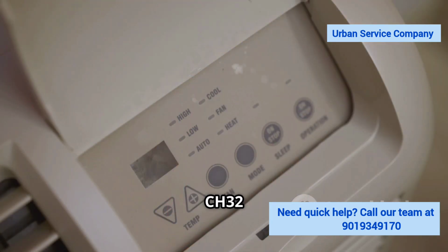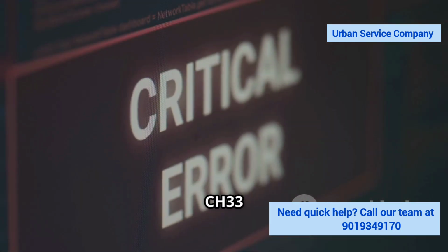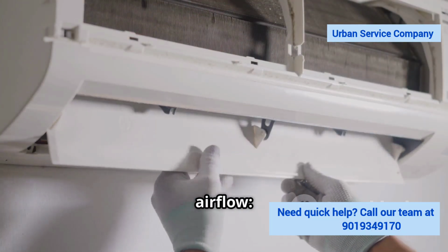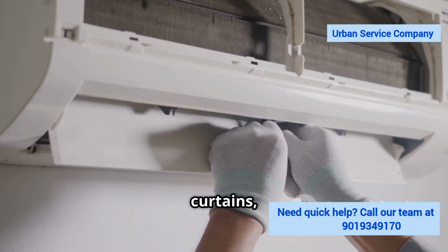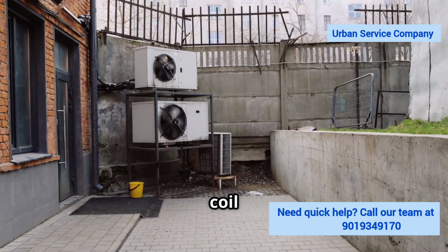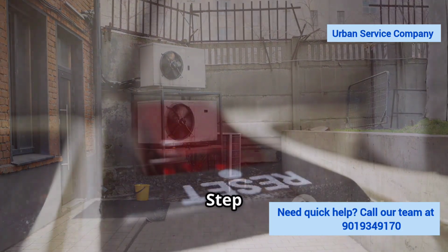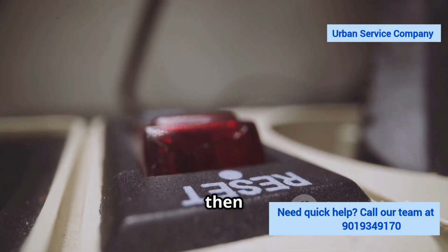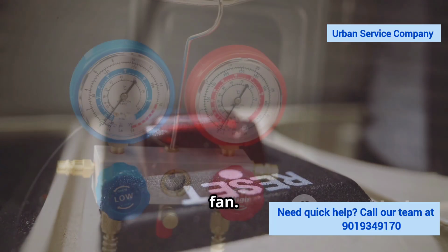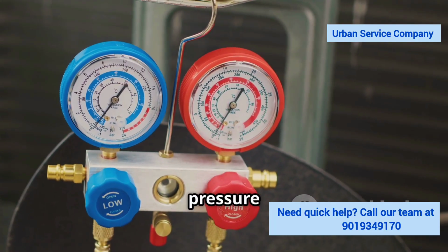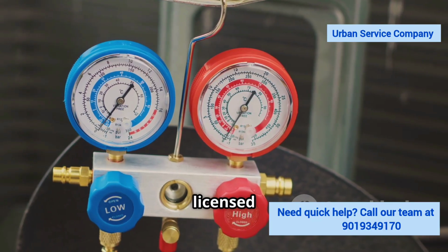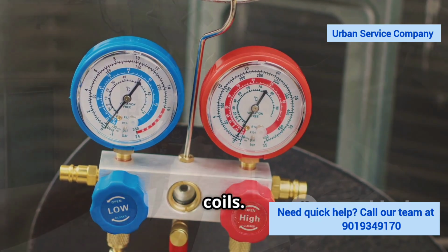Code CH32, high pressure. Code CH33, low pressure. Step 1. Inspect airflow. Indoor filters, curtains, and doors. The outdoor coil must breathe on all sides. Step 2. Reset power, then test on cool mode and medium fan. Step 3. Recurring pressure faults need gauges. Have a licensed tech check refrigerant charge and coils.